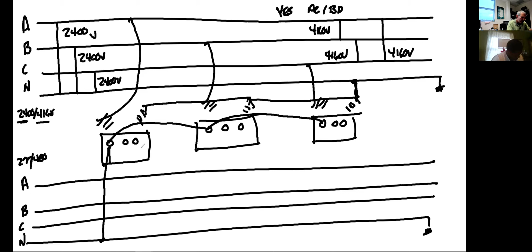So I'm going to say the left-hand bushing on all of my transformers that I've converted to AC BD is going to be my neutral bushing. Left to left to left, to neutral, that's my neutral. What's left? Remember, I've only got 3 legs and bushings to use. Real easy here guys: A, B, C. So my left-hand bushing is neutral on all 3 transformers. Bang, bang, bang. My right-hand bushing is where my BD is at, is my hot wire.